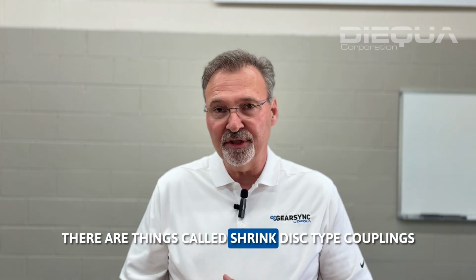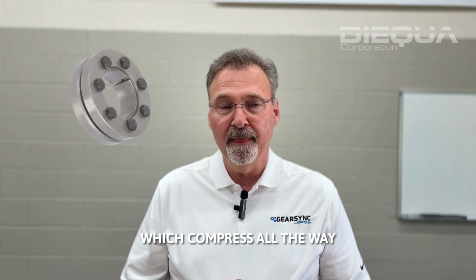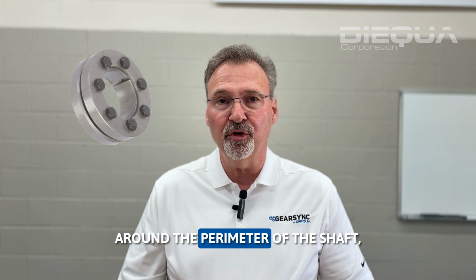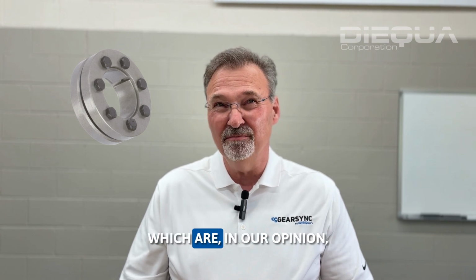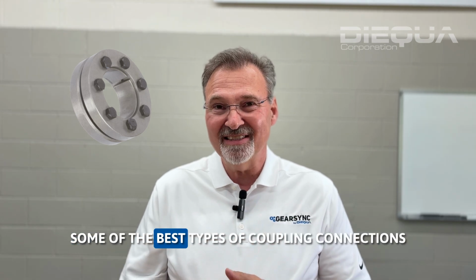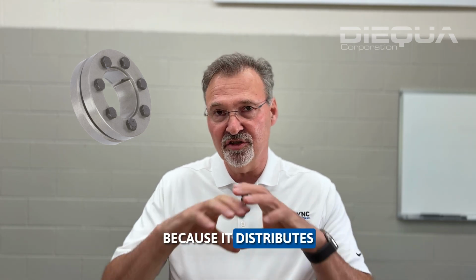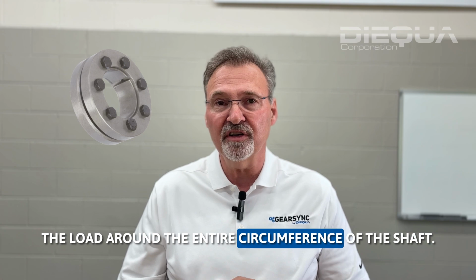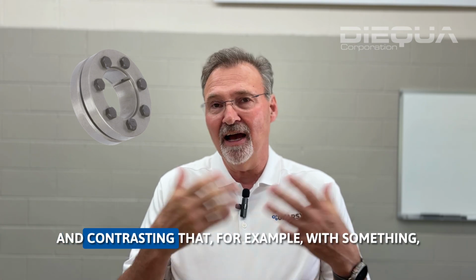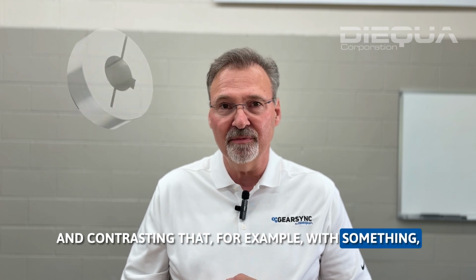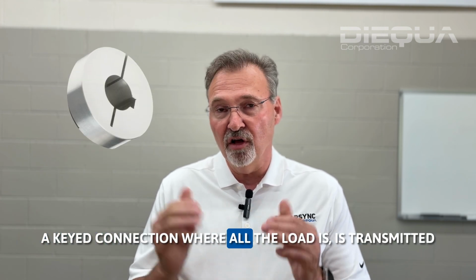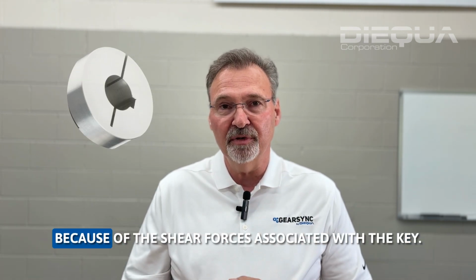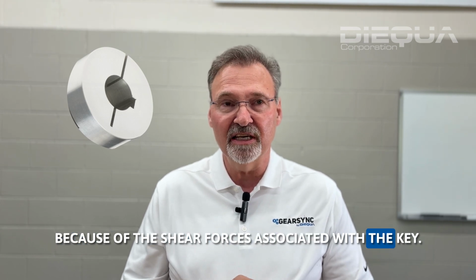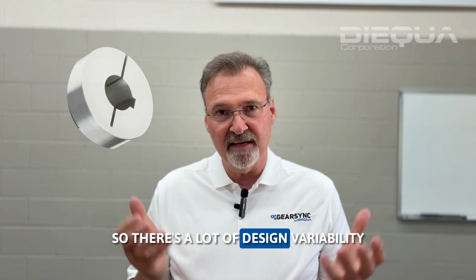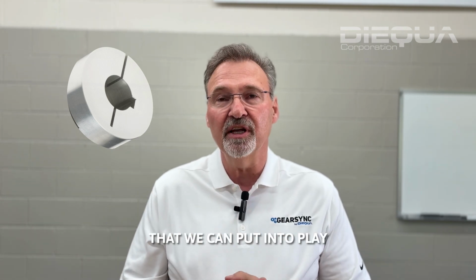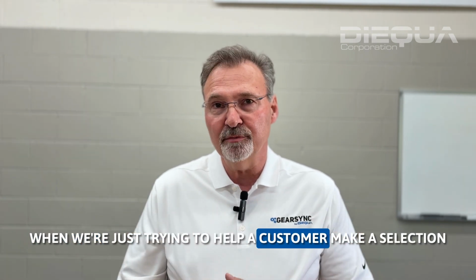There are shrink disc type couplings, which compress all the way around the perimeter of the shaft, which are, in our opinion, some of the best types of coupling connections because it distributes the load around the entire circumference of the shaft. Contrast that, for example, with something like a keyed connection, where all the load is transmitted because of the shear forces associated with the key. So there's a lot of design variability that we can put into play when we're just trying to help a customer make a selection.